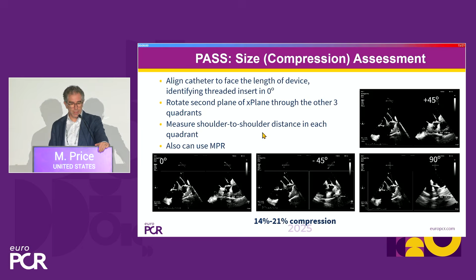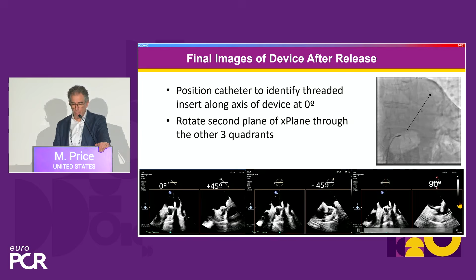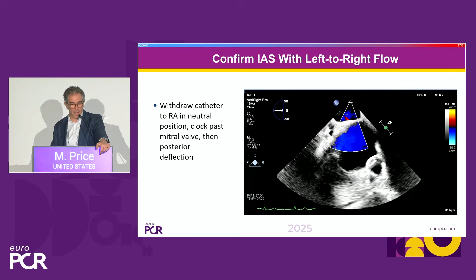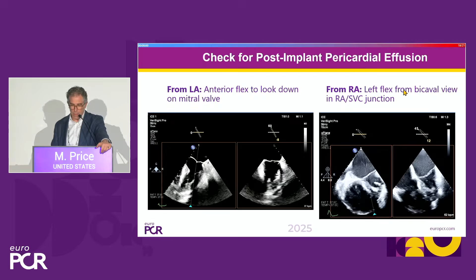And again, if you look at the image here, my ICE catheter is looking straight up at the face of the device. And in my 0 degree, I see the threaded insert, so I know I'm slicing down the middle of the device. So my diameters are correct. I've just gone through the 4 quadrants and recorded them, and I have a beautiful position of this device. And then when we're done, you can quickly do the things that an echocardiographer would do, or at least tell me that I need to look at, and that's to make sure that you have left to right flow across your interatrial septal defect. You also want to look for a post-implant effusion. You can either just from the left atrium look down on the mitral valve, something that Goggin will talk a lot about when he talks about ICE-guided mitral TEER. Or you can do that technique from the right atrium where you see the 4-chamber, and again, there's no effusion.